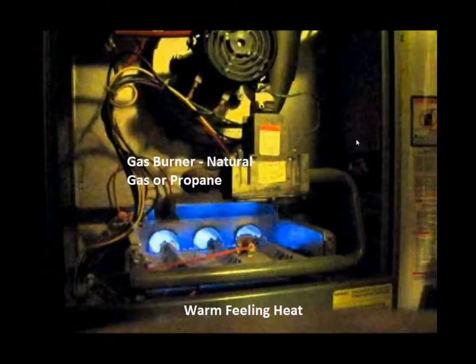Below 32 degrees, something like this burner would be more efficient. But again, usually it's one or the other, and the gas heat feels so much warmer. If you walk by a register, it may be blowing out 100+ degree air on you, whereas a heat pump may only be blowing 85 degree air, and your skin temperature may be warmer than 85, so it may still feel cool.